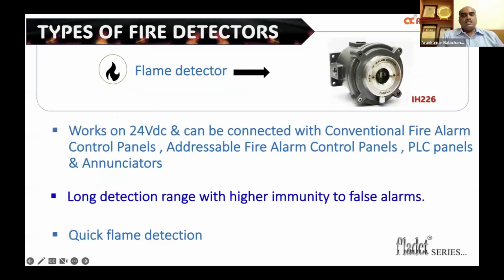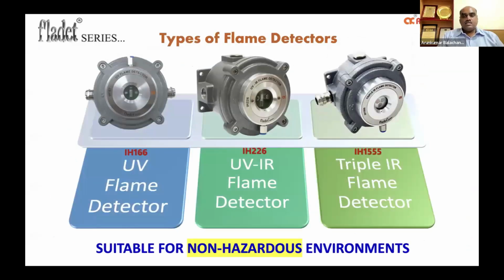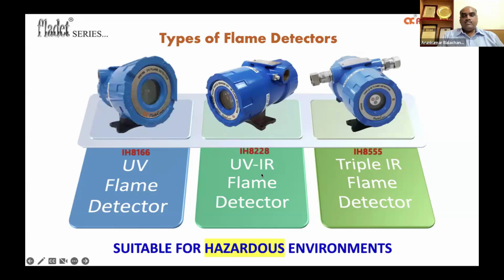The flame detectors, as I said, have a longer detection range, and they are also highly immune to false alarms. These detectors can be connected to any conventional or addressable or even PLC or annunciator panels. These are some of the flame detectors that are available, which are widely used in a lot of industries. The IH226 detector is very widely used in many industries for non-hazardous applications. These are the flame-proof type detectors, where if the environment is explosion-proof or flame-proof, we can use the X-proof type of flame detectors.